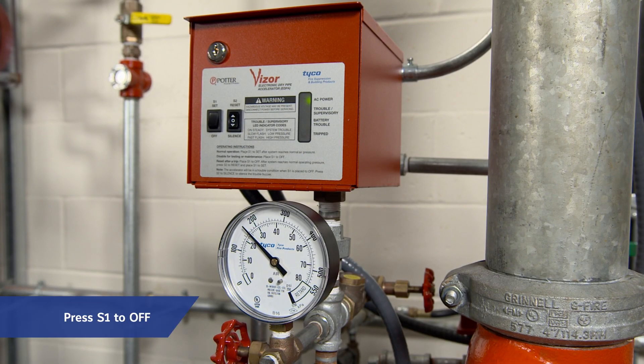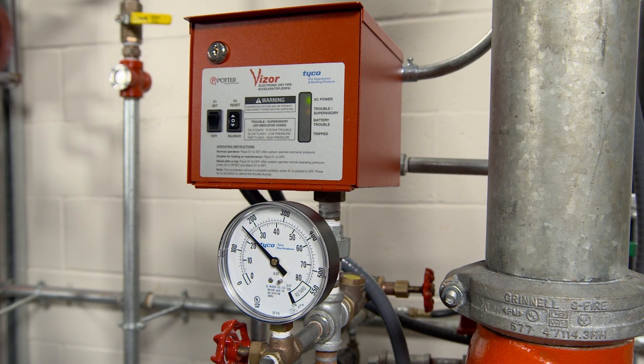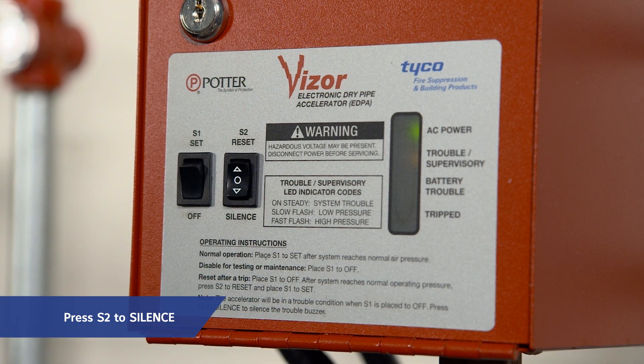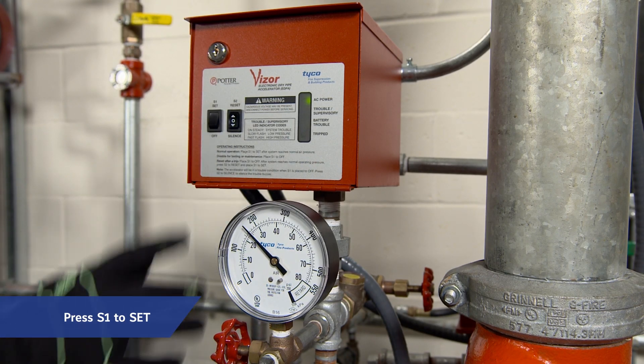For maintenance of the system, place S1 to off. Air pressure should still be at normal operating levels. Silence the local alarm from the Vizor unit by placing S2 to silence. Once maintenance or testing is complete, place S1 to set.